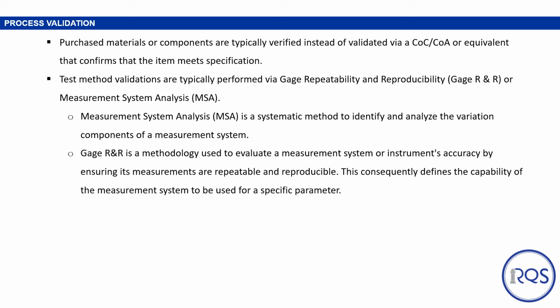Test method validations are typically performed with gauge R&Rs or measurement system analyses. A measurement system analysis, or MSA, is a systematic method to identify and analyze the variation of the components of a measurement system. MSA is used as the checkpoint of data quality before we start any further analysis or draw any conclusions from the data. A gauge R&R is a methodology used to evaluate a measurement system, such as an instrument, and that instrument's accuracy by ensuring that its measurements are repeatable and reproducible. This consequently defines the capability of that instrument to be used for a specific parameter or dimension.